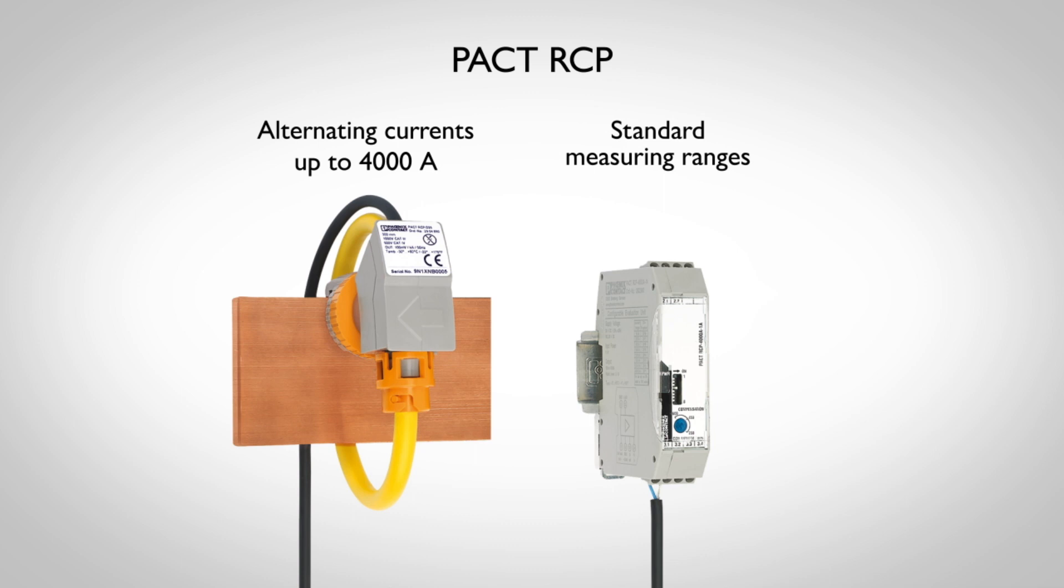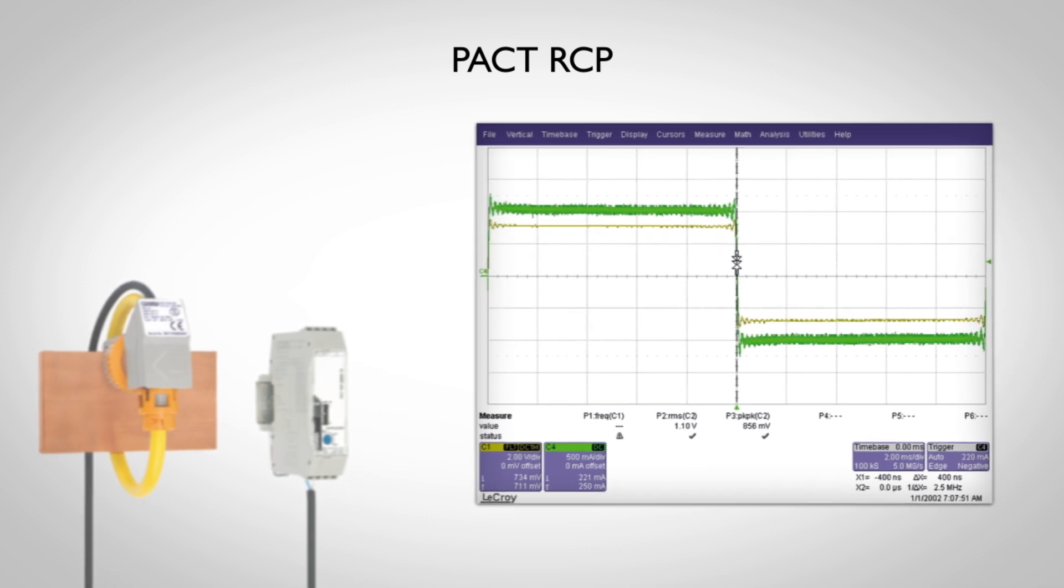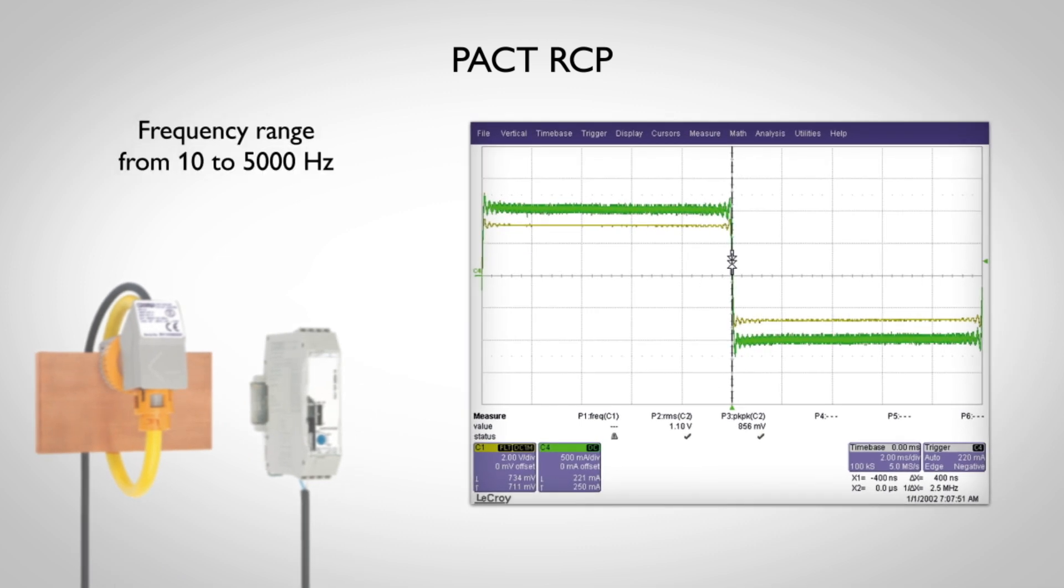The absence of an iron core results in a wide frequency range of 10 to 5000 Hz, thereby enabling transients and harmonics to be detected with phase accuracy.